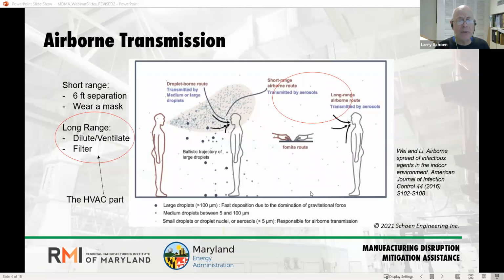In the box in the middle of the slide, it shows you graphically these very large dots from the person in the middle settling to the ground and not reaching the adjacent person. The person on the left, however, is blowing a cloud of respiratory aerosols, quite frankly, directly at this other person, which we want to try to avoid. The person farther away to the right is the one that we believe we can protect to some extent with the HVAC system interventions. And then in the middle where you see these two hands and the fomite route label, that's again something that we generally cannot affect with ventilation. This is more of a behavioral and surface cleaning issue that you've heard so much about.